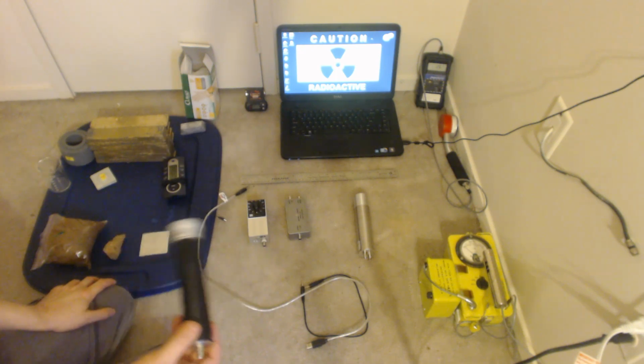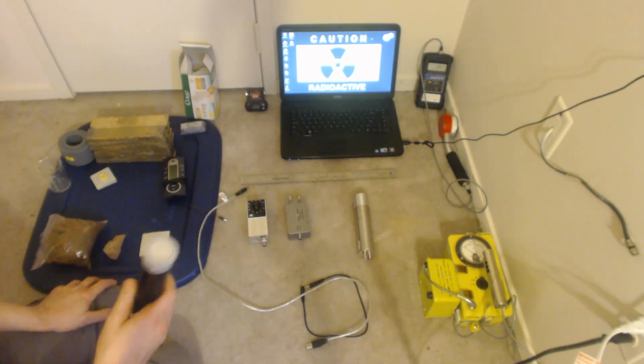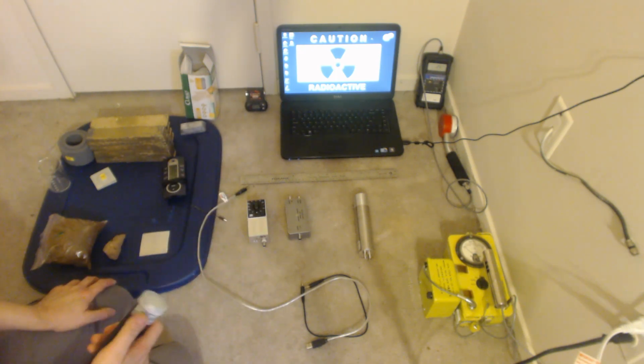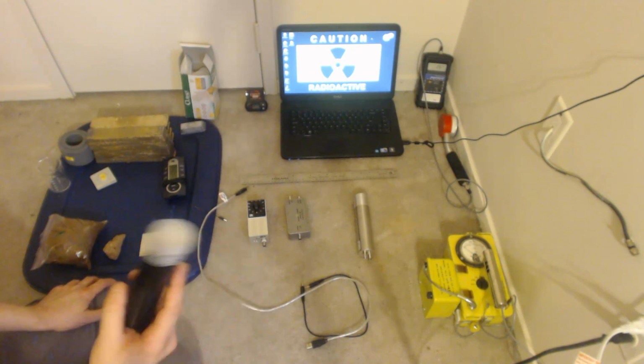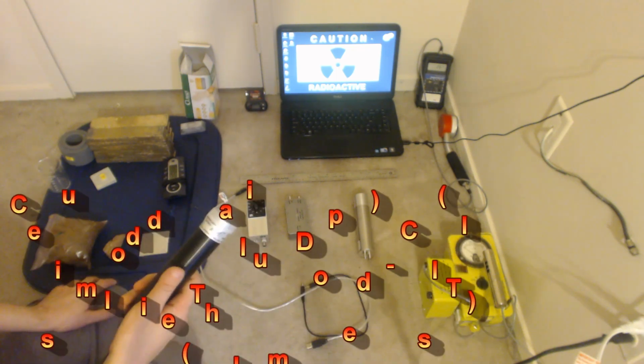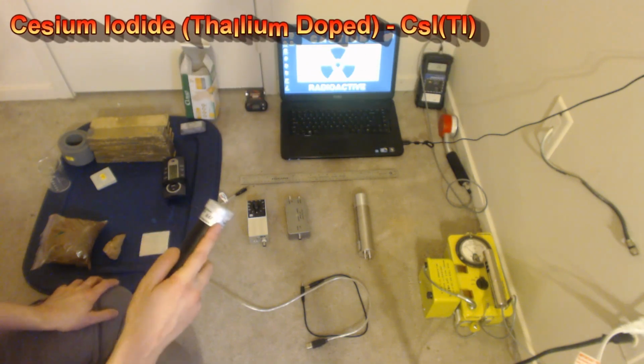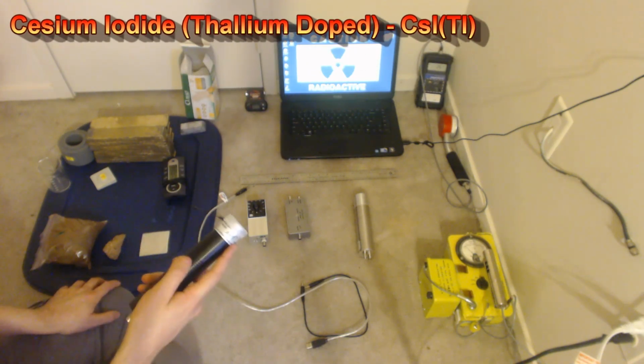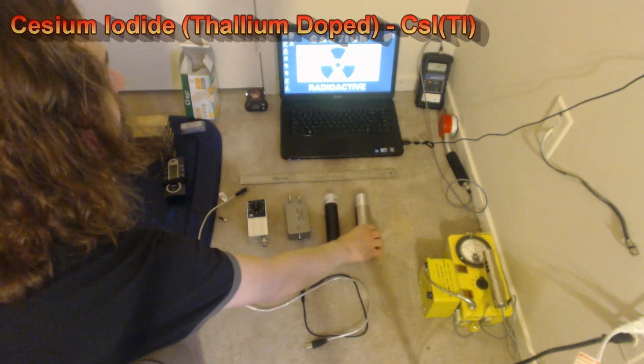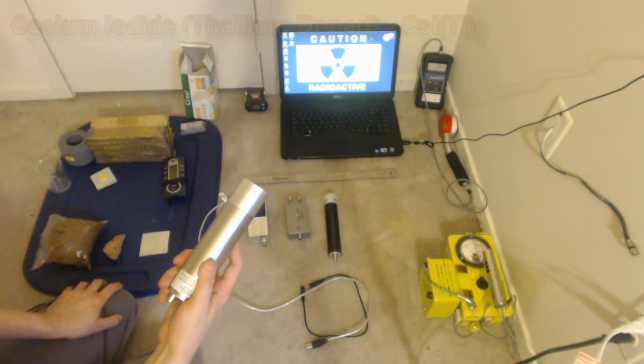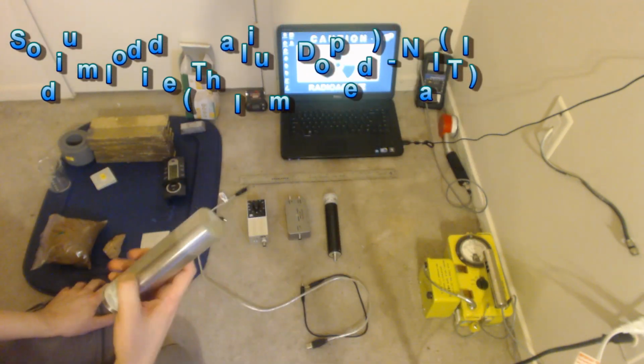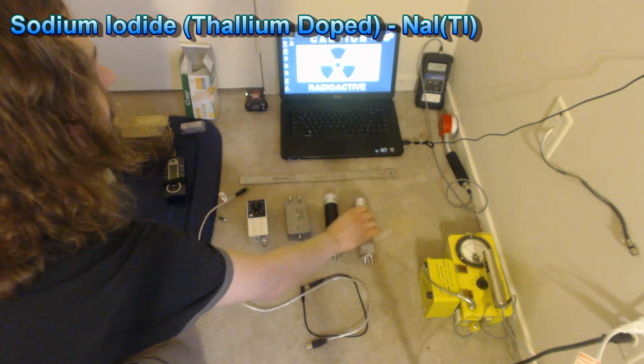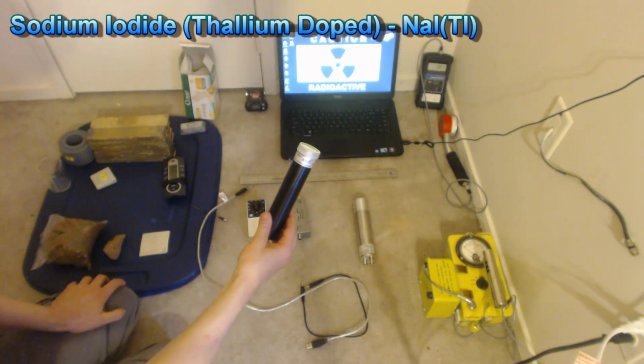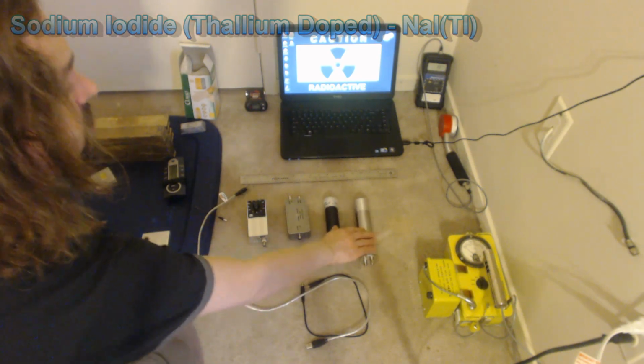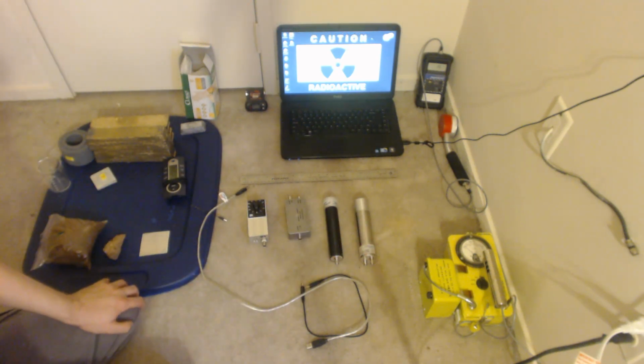There are many types of detectors, from micron plastic scintillation detectors. These are scintillators, by the way, BGOs, and so on. But two of the most common ones used for gamma spectroscopy are going to be cesium iodide, CsI(Tl), if you've ever seen it before, and sodium iodide, NaI(Tl). And the cesium iodide typically seems to be a little bit more rugged, but the sodium iodide produces a better quality spectrum, typically speaking.